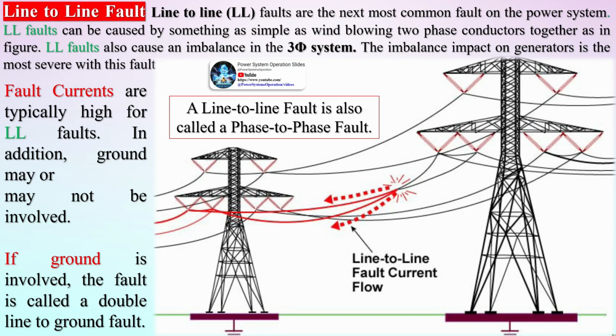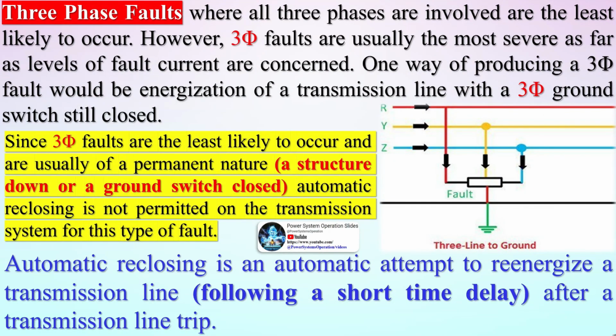on the power system. The closer the fault is to generators, which are the source of voltage on the power system, the greater the fault current can be. The fault current is larger because there is less impedance between the fault and the source, the generator. Fault current values in the tens of thousands of amps are common on the high voltage transmission system. The term short circuit means that an unusually low impedance current path has been formed. Typically, a short circuit involves bypassing the load impedance.